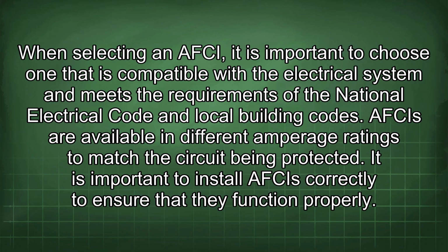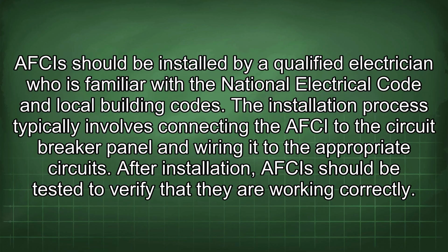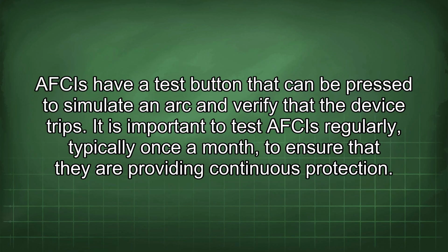It is important to install AFCIs correctly to ensure that they function properly. AFCIs should be installed by a qualified electrician who is familiar with the National Electrical Code and local building codes. The installation process typically involves connecting the AFCI to the circuit breaker panel and wiring it to the appropriate circuits. After installation, AFCIs should be tested to verify that they are working correctly. AFCIs have a test button that can be pressed to simulate an arc and verify that the device trips.